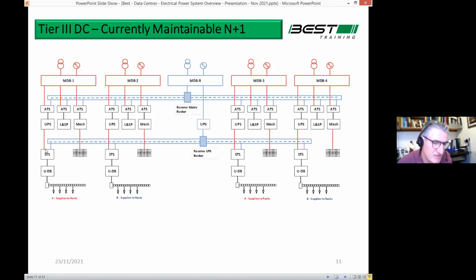The critical load is able to draw its supply off this UPS or this one. So that's a typical arrangement. We call that a tier 3 data center. Tier 3 is usually what they call an N+1 arrangement. So this N+1, which we again will cover in a few slides, means you need N plus 1.